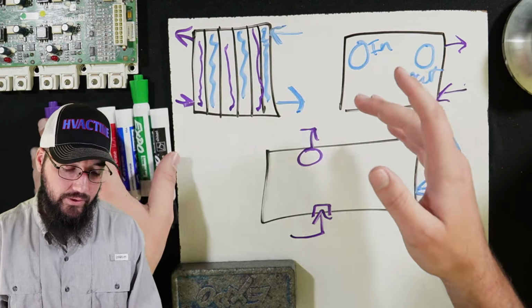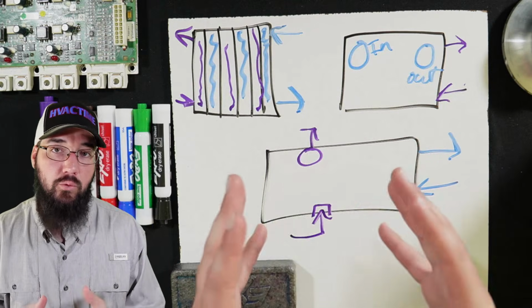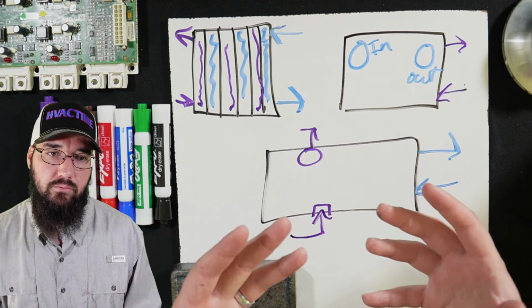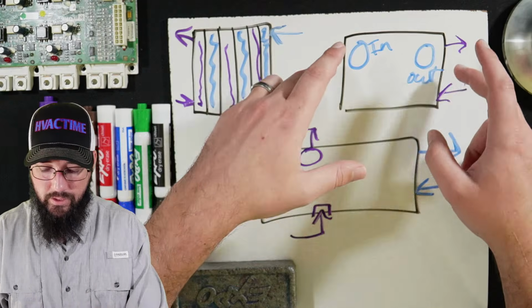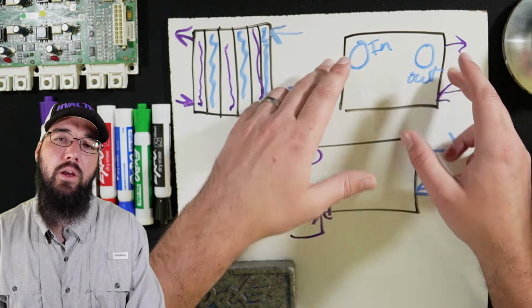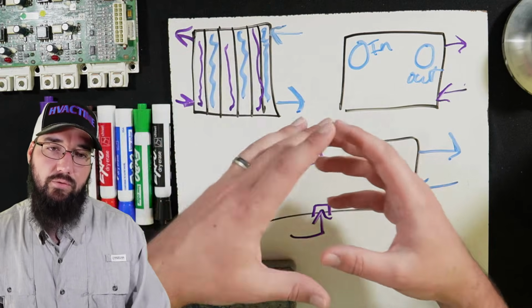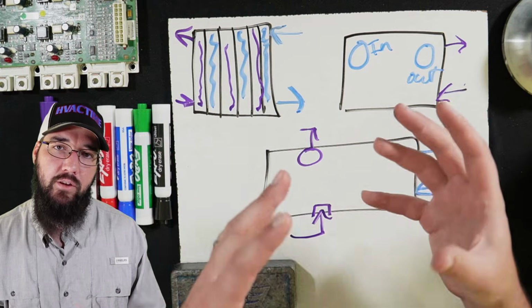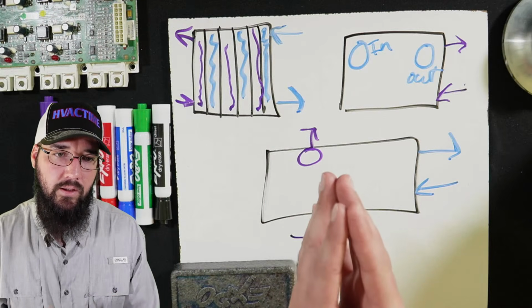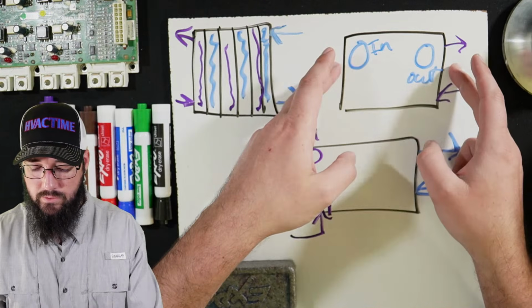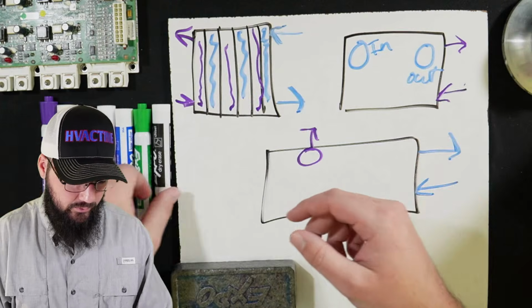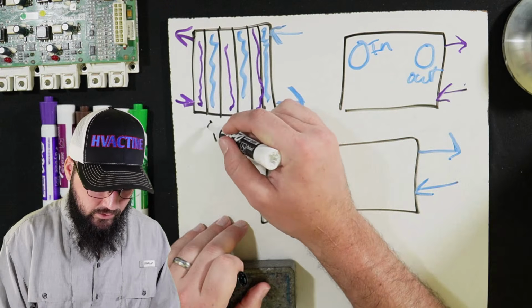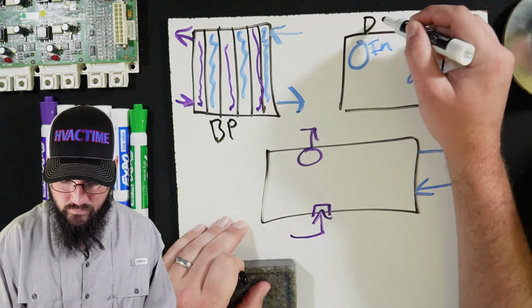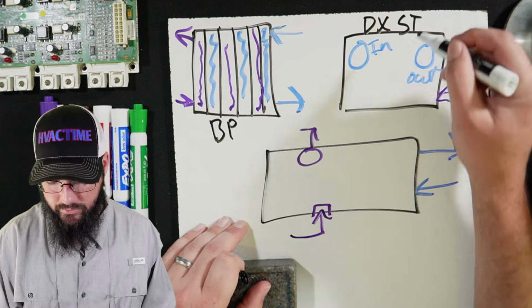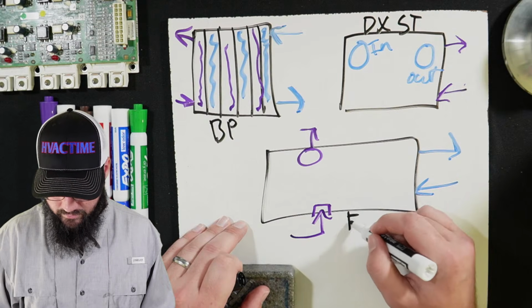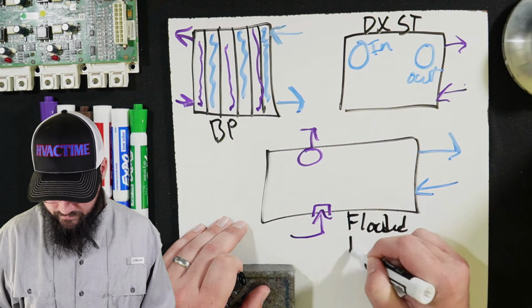Okay, my understanding, braze plate, they're smaller, they're more compact, and they're a cheaper device to my understanding. And when we get into a DX shell and tube, these are difficult to scale, especially within the format of, say, an air-cooled chiller or something. Where these, the DX shell and tube, scale much better. Let me actually label these. So we have a braze plate, direct expansion shell and tube, and then we have a flooded falling film.